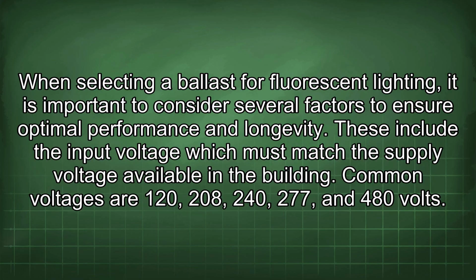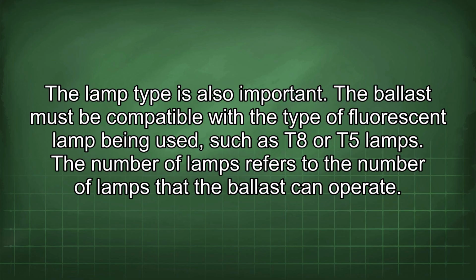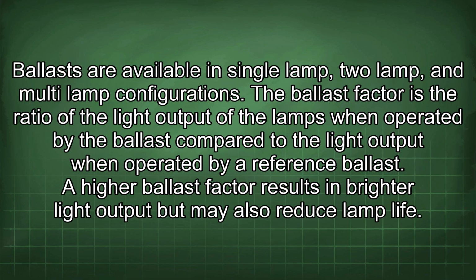Common voltages are 120, 208, 240, 277, and 480 volts. The lamp type is also important. The ballast must be compatible with the type of fluorescent lamp being used, such as T8 or T5 lamps. The number of lamps refers to the number of lamps that the ballast can operate. Ballasts are available in single lamp, two lamp, and multi-lamp configurations.